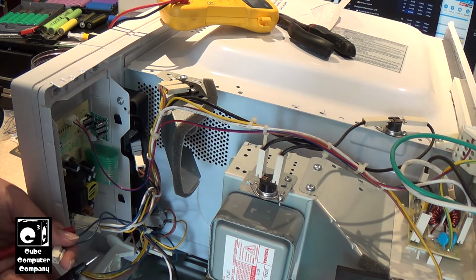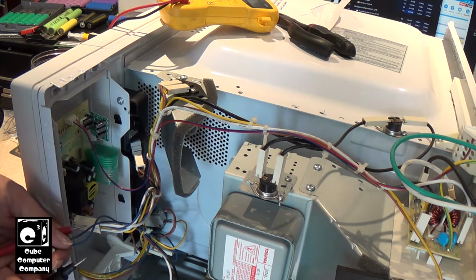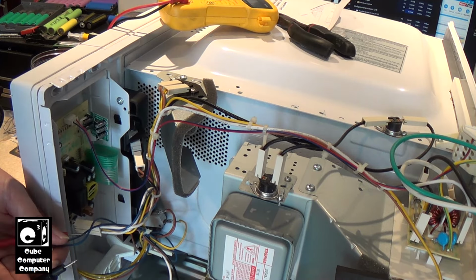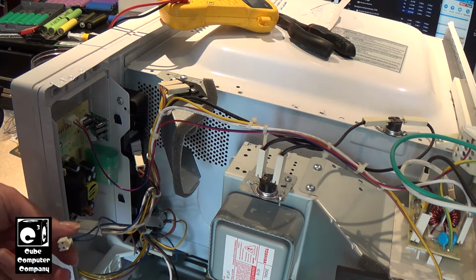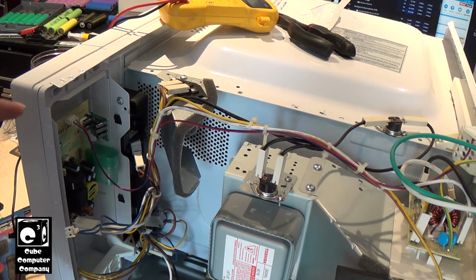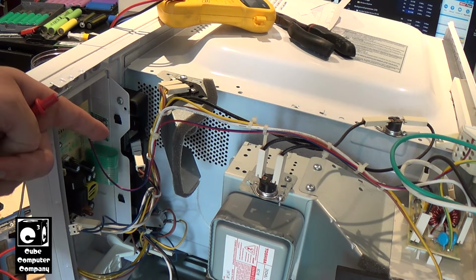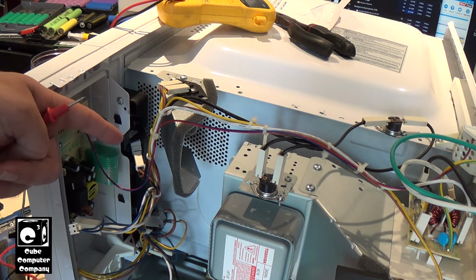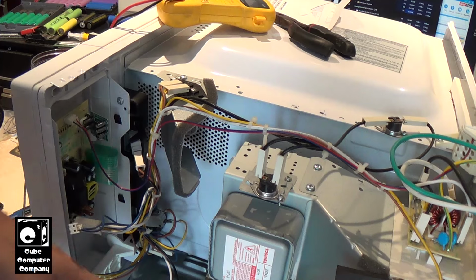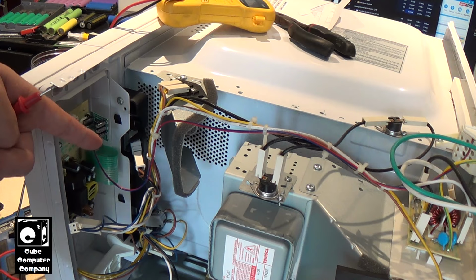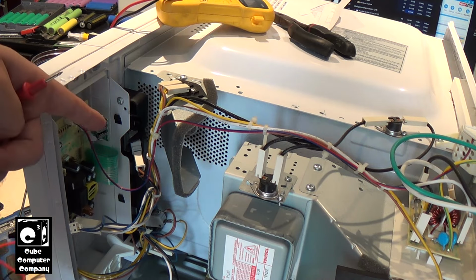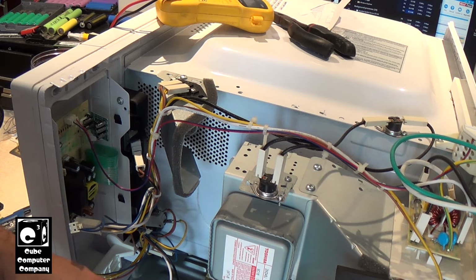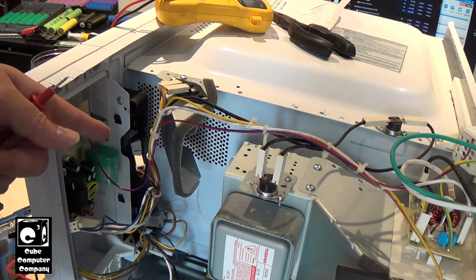Okay, so I've taken a moment to test all three of these micro switches in here, and they all test good. So let me go ahead and explain how these work. We have two that are normally open. You have the primary interlock switch, which is up top. This one kills power to the transformer down here. This one actually has primary 120 volts going through it. And when this one breaks, it kills power to the transformer. So let's say if this one fails to work.